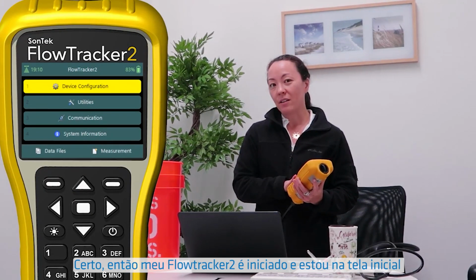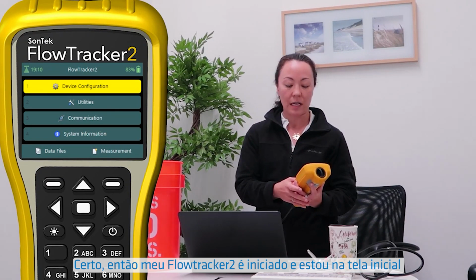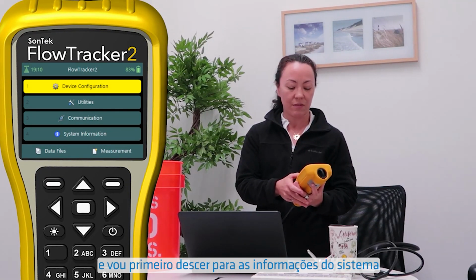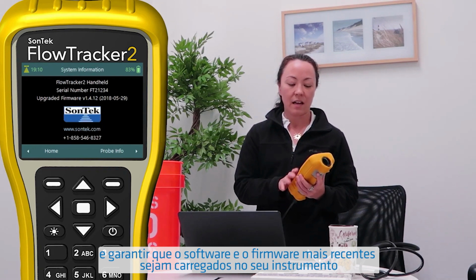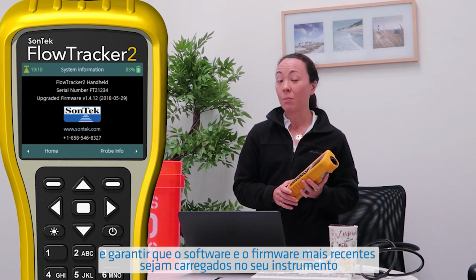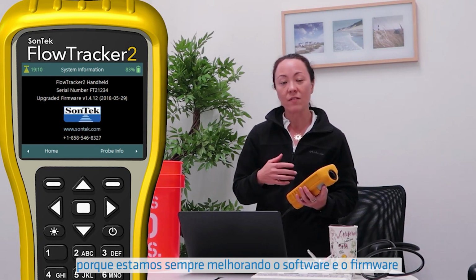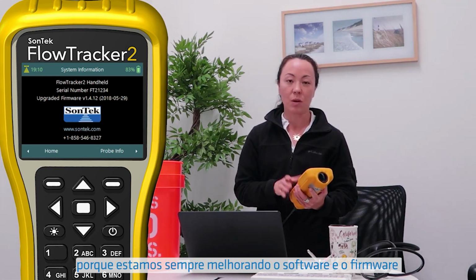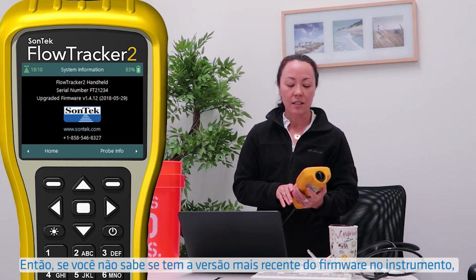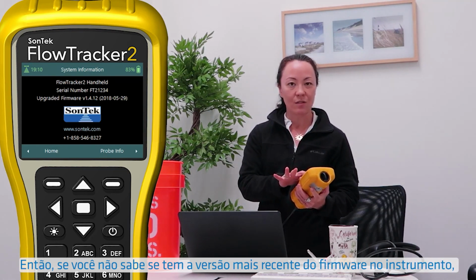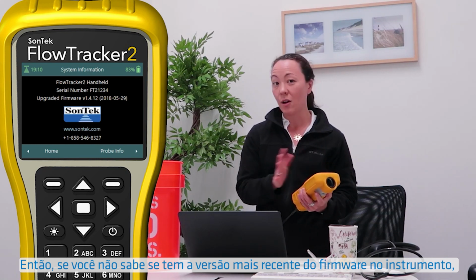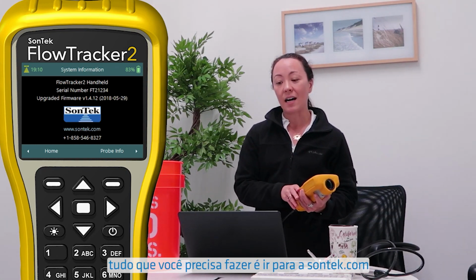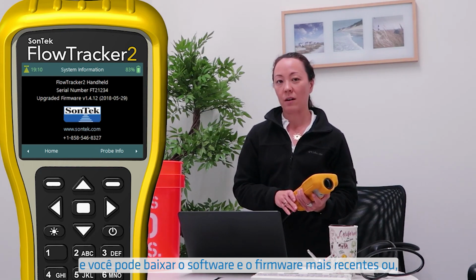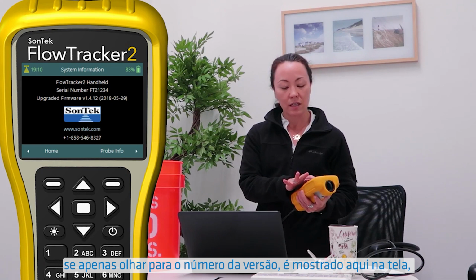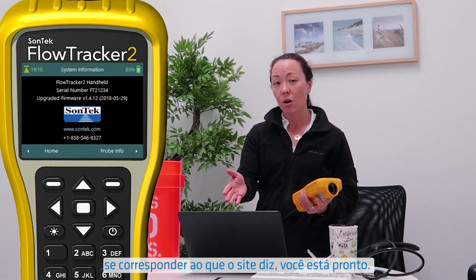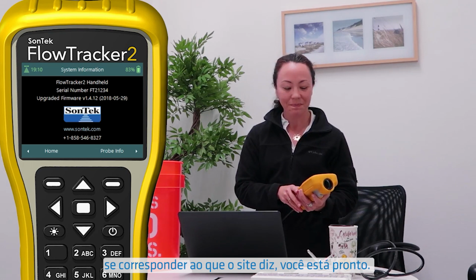All right, so my FlowTracker is booted up and I'm at the home screen. I'm first going to go down to system information and just make sure that the latest software and firmware are uploaded to your instrument, because we're always improving the software and firmware, and you want to make sure that's to your advantage. If you don't know if you have the latest version of firmware on the instrument, all you have to do is go to sontek.com and you can download the latest software and firmware. Or if you just look at the version number, it's shown here on the screen. If it matches what the website says, you're good to go.